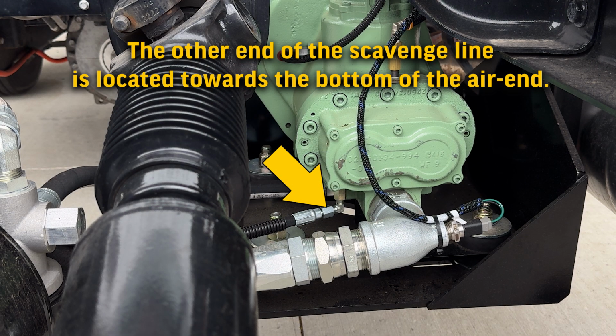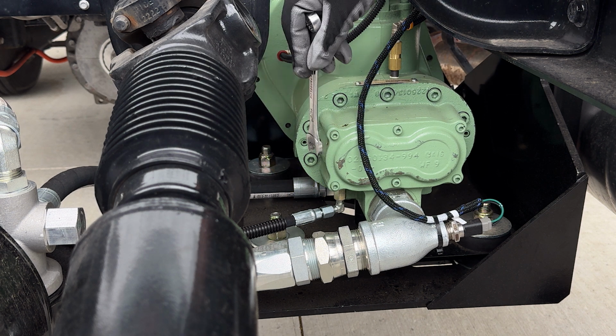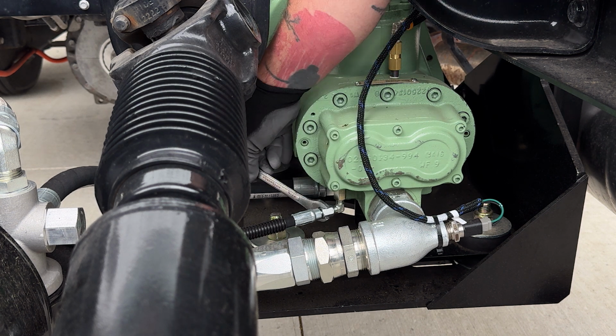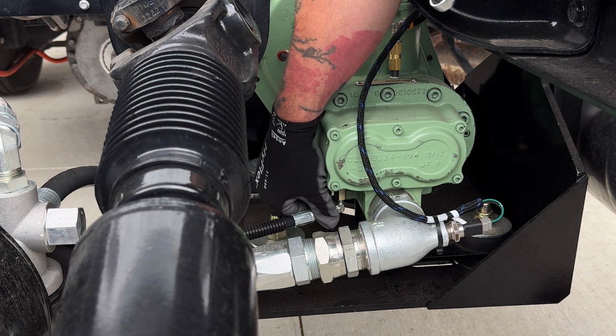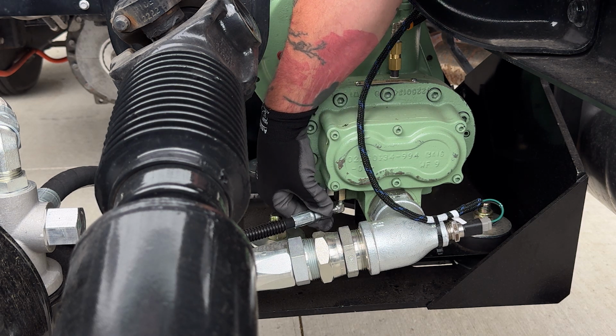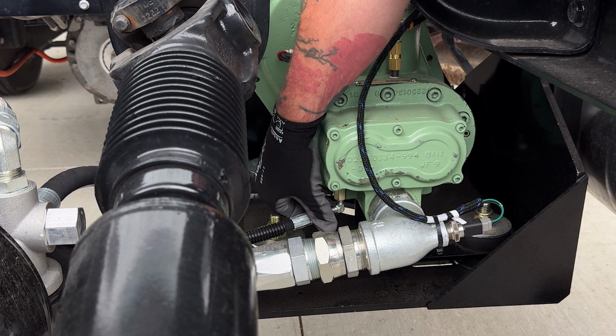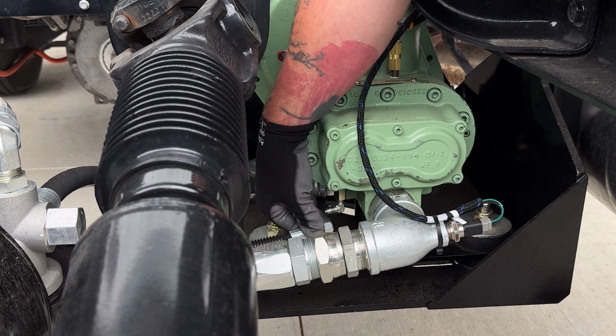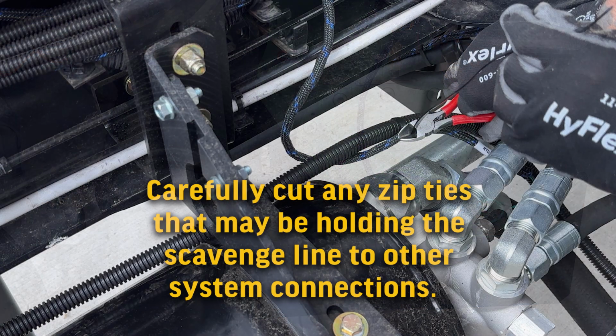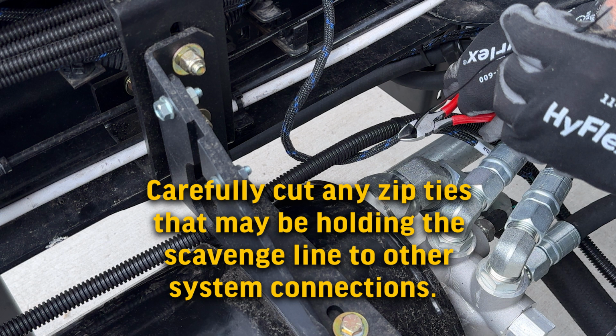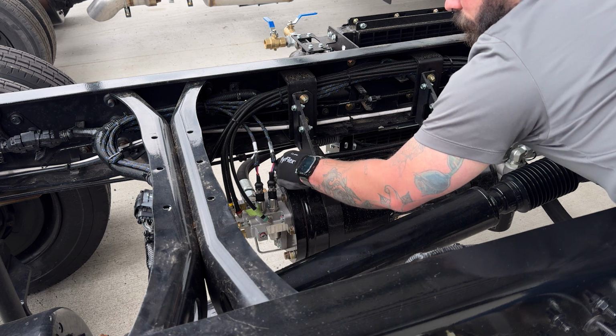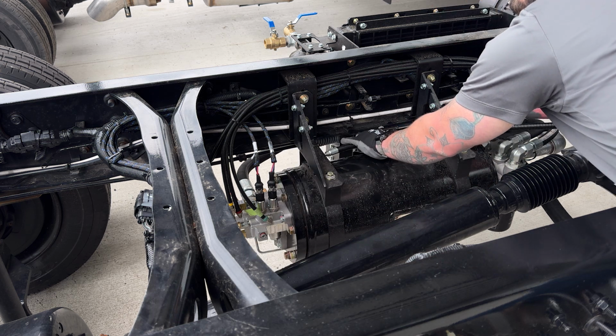The other end of the scavenge line is located towards the bottom of the air end. Using a 9/16 open-ended wrench, loosen and remove the scavenge line on the air end. Carefully cut any zip ties that may be holding the scavenge line to other system connections. Carefully remove the scavenge line from the underdeck system.